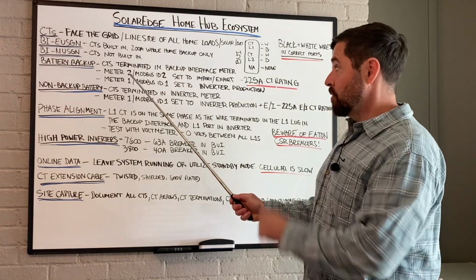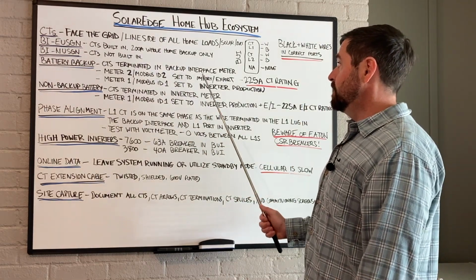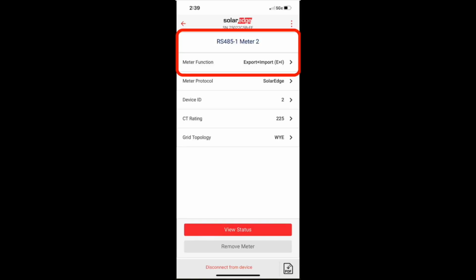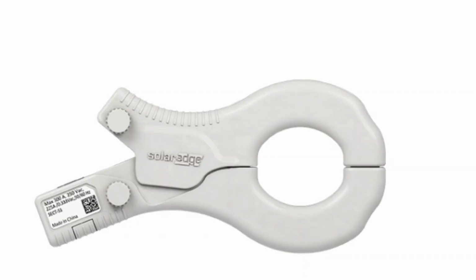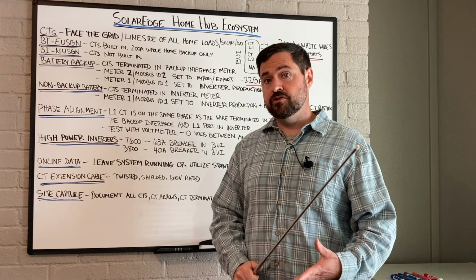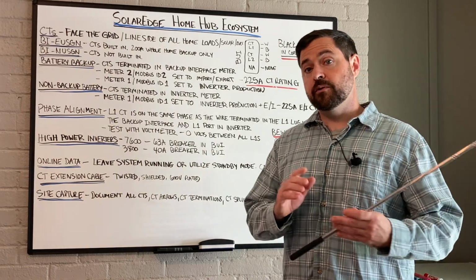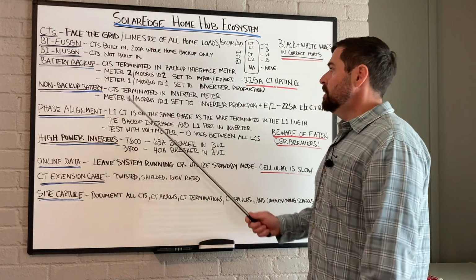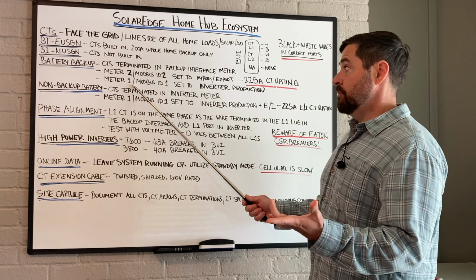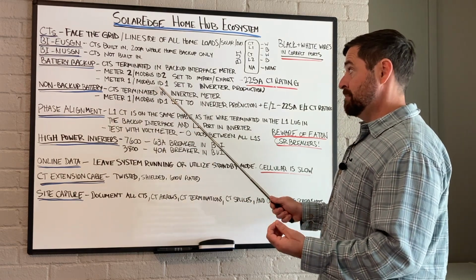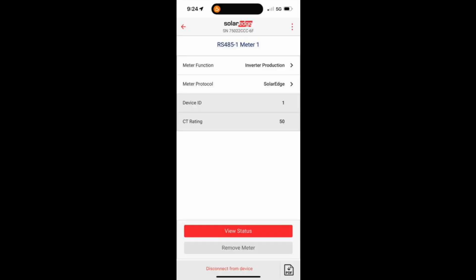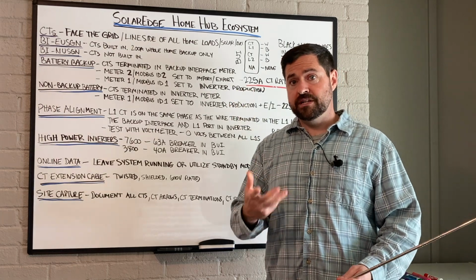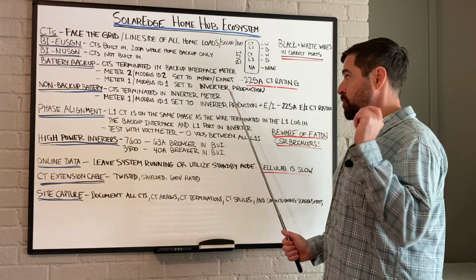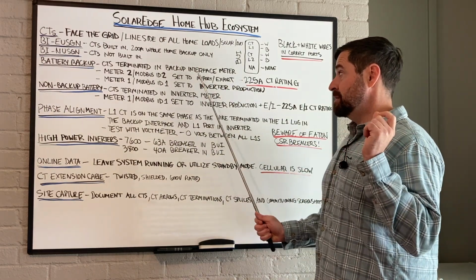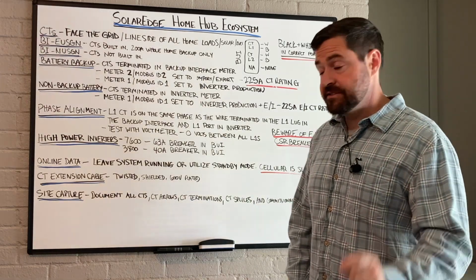So in this case, you're going to program meter 2, or Modbus ID 2, to import, export. You also always need to make sure that the CT rating is 225 amps. Those slim clamp-on SolarEdge CTs are 225 amp CTs. If you make any other choice there, commonly people choose 200, it's going to make the readings incorrect. And then for meter 1, or the solar inverter energy meter, we're going to set that meter 1, or Modbus ID 1, to inverter production. Again, because the built-in production CTs are factory installed into that energy meter and the inverter. So you're going to pull inverter production from the energy meter and the inverters. You're going to be pulling the consumption data from the backup interface.